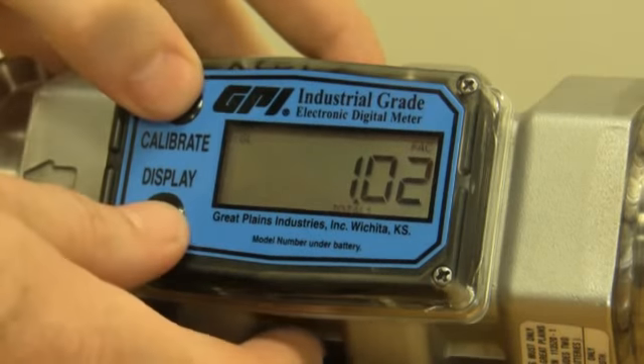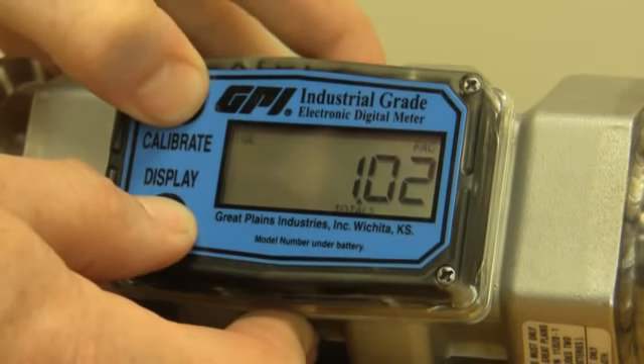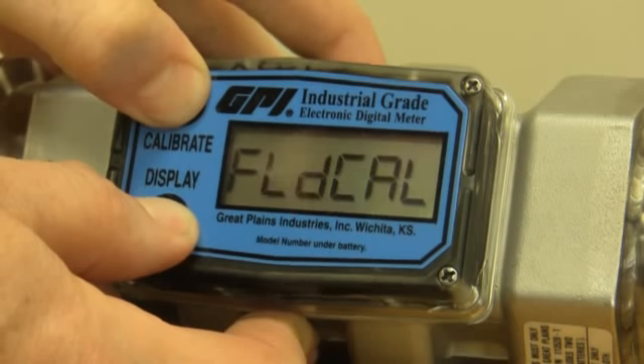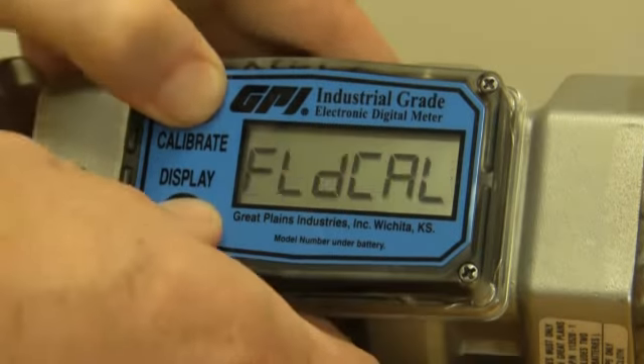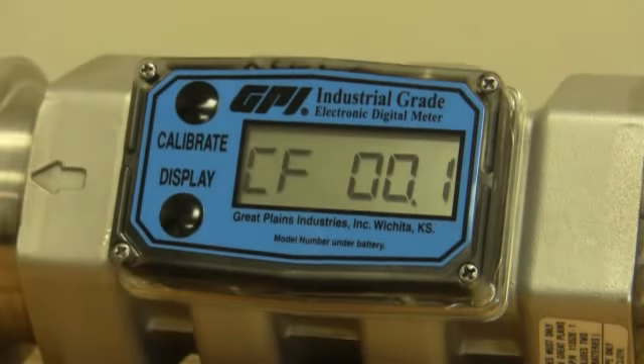So first thing you're going to do is hold down both buttons. You just keep holding until it says Field Cal. When you let go, it's going to give you CF and then a number. CF stands for correction factor, which for all intents and purposes is a percentage. So what we're going to do is change the factory calibration by a percentage.